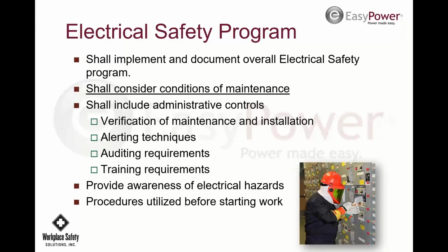And some people think they'll put a shield on and they're good to go, and in reality they should have had a suit on because it's a much higher arc flash because the fault current is worse than it was. That's why it's required to be done every 5 years, so that when there are changes in fault current or changes in anything in the system, you're updating it to reasonable levels and not letting it get out of hand.